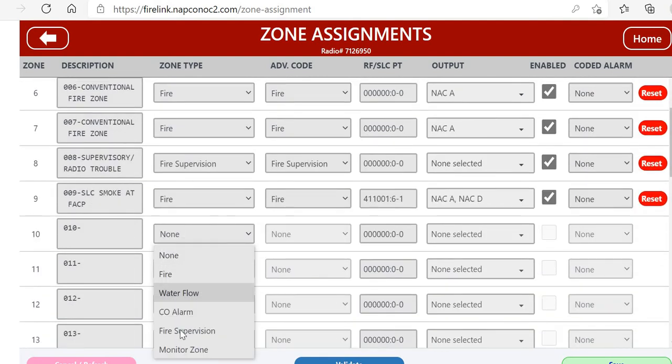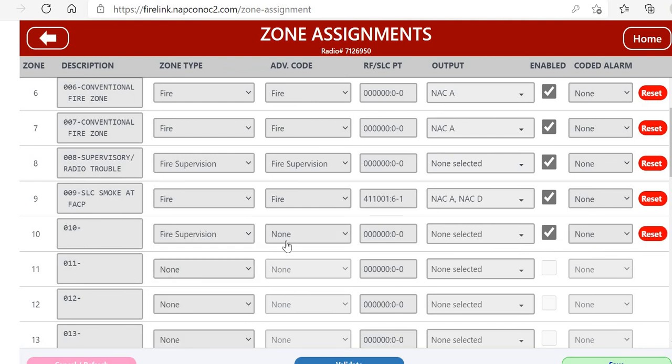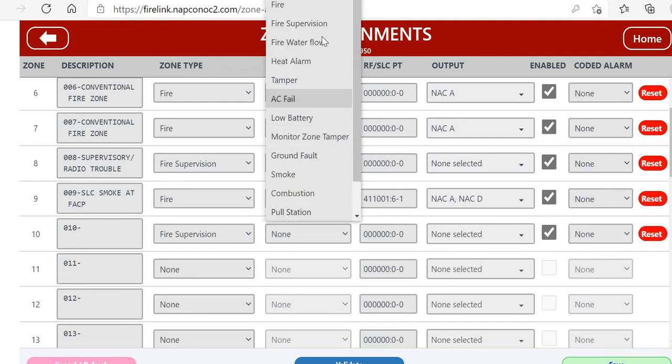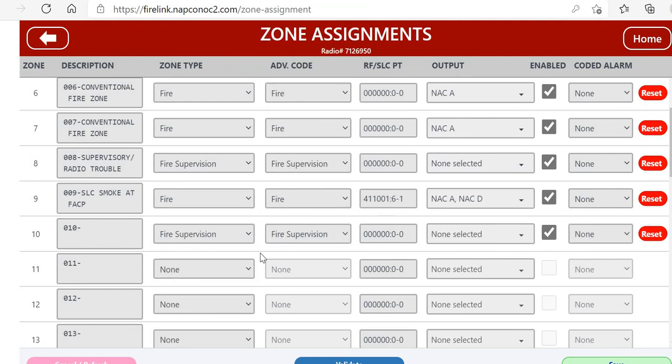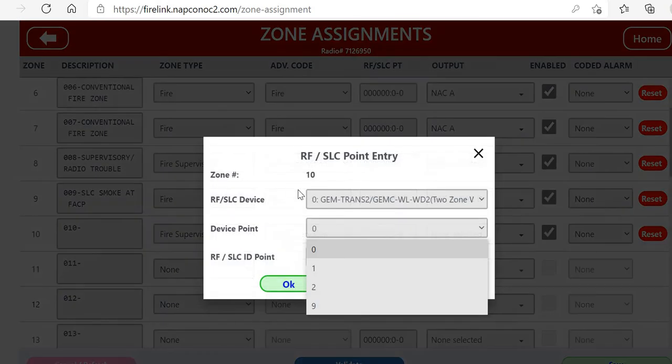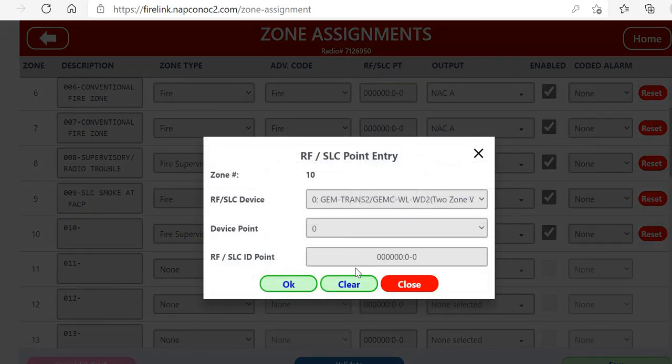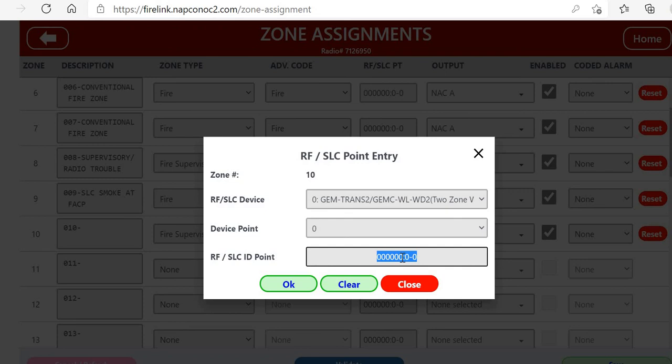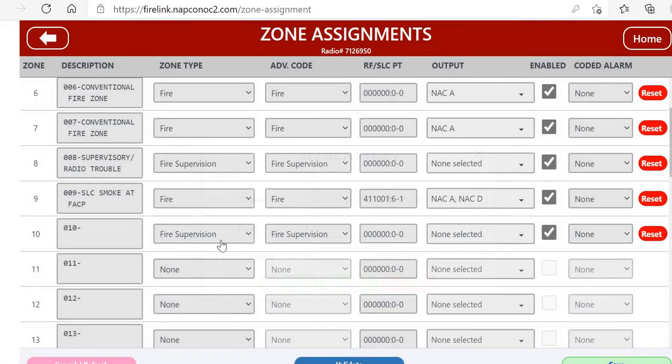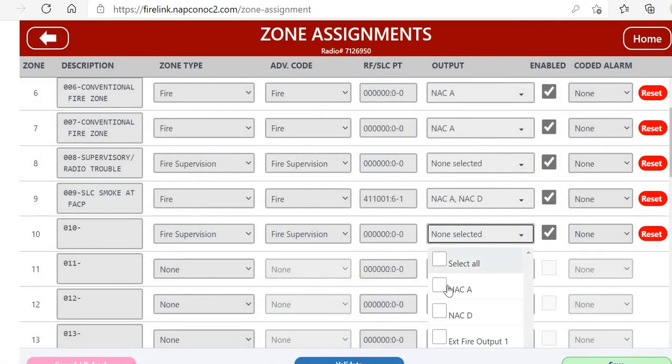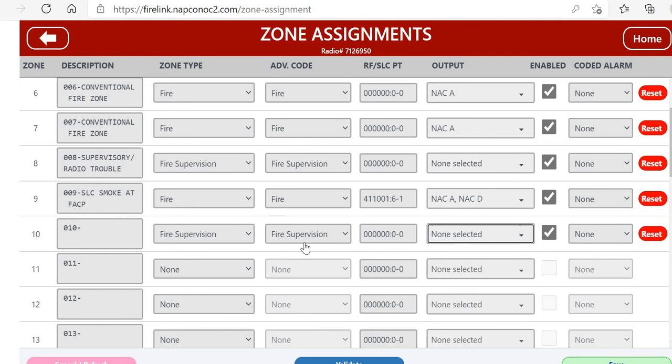Same thing, we will go back to our Zone Assignment section. We would make this a supervisory zone. We'll pick the advanced code of fire supervision so it reports that. Same principle, we would click on this and this is where we would type in the RFID of the smoke detector or the heat detector or the WLWD2 module. Same thing, we would pick our NACs if we had any outputs. We're going to have none because this is a supervisory type zone, and click enabled and then Save.